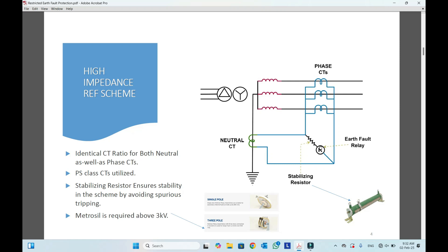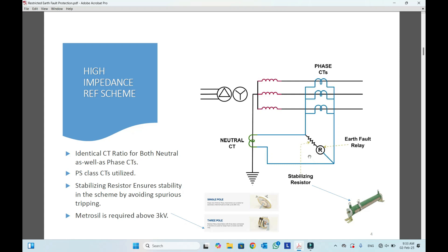Because it's a high impedance relay, we need to connect a stabilizing resistor. Due to CT inefficiencies or external fault conditions, a little current could flow. To limit this current we need this stabilizing resistor, and also we need one metrosil. You can see one single pole or three pole metrosils connected in parallel to this relay and resistor, because in the case of an external fault a high secondary voltage will develop, and if high secondary voltage develops there is a chance that high current can flow through this relay and operate it, and even burn our resistor if the current continuously passes. So we apply one metrosil.